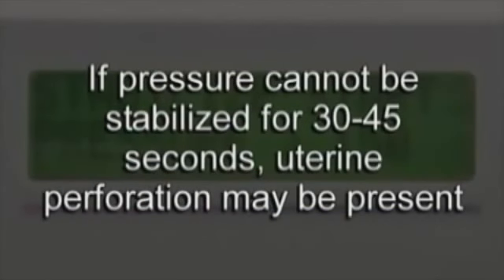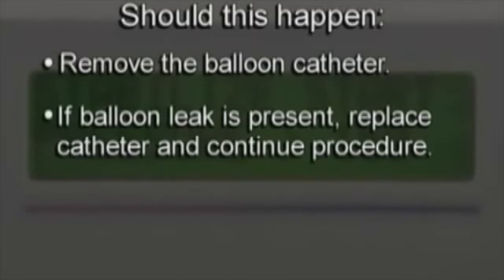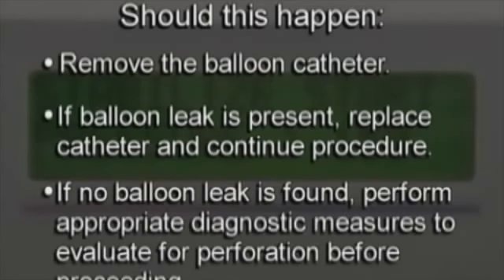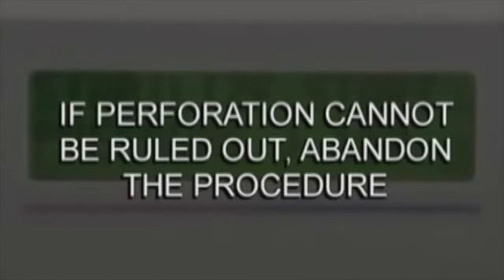Important: if pressure cannot be stabilized at 160 to 180 millimeters of mercury for 30 to 45 seconds with up to 35 milliliters of fluid, this may indicate uterine perforation. Should this happen, remove the balloon catheter. If a balloon leak is present, replace the catheter and continue with the procedure. If no balloon leak is found, perform appropriate diagnostic measures to evaluate for perforation before proceeding. If perforation cannot be ruled out, abandon the procedure.